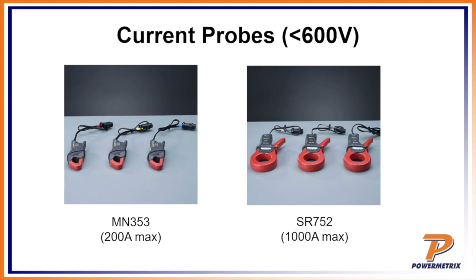The other option is using an SR752 - let's switch back over here to Ray and talk about those. You've got the SR752s, good for 1,000 amps, and you've got a direction of current flow here. So all of our probes have these arrows on the side, so you need to make sure that arrow follows the direction of current flow. They work really good in the meter can.